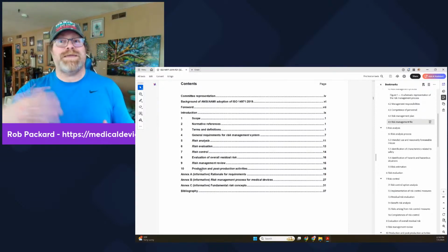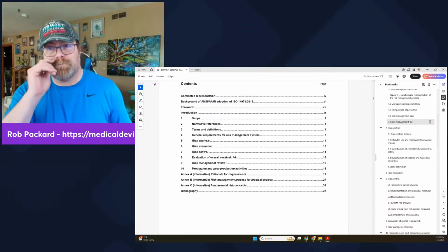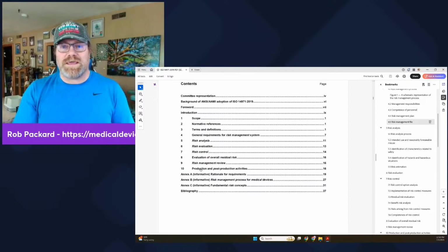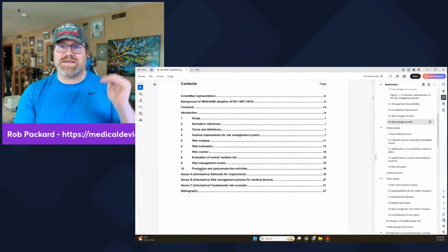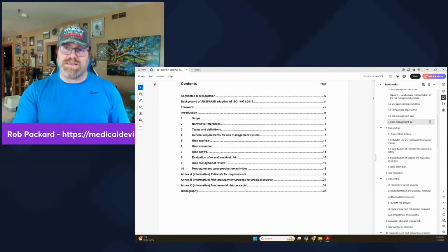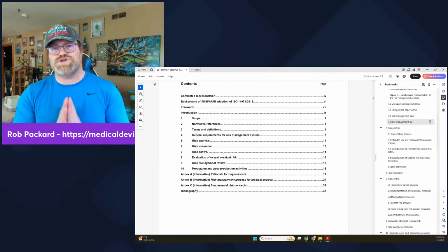When in doubt, estimate higher risk, estimate higher probability, and then when you gather real post-market data, you can reduce it. That would be the continuous updating, the living document. So you don't have to worry about being perfect. You can estimate high and adjust it later because it's a living document. They're not etched in stone. But a simple 5-point scale is what I recommend. And particularly for severity, which is the most important, I try to keep it simple. The FDA likes it simple too.